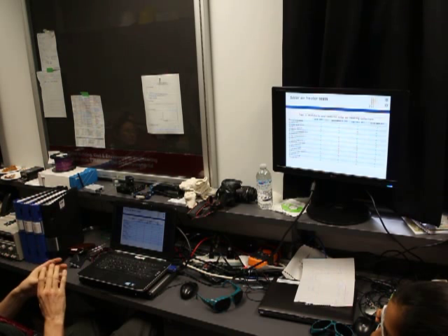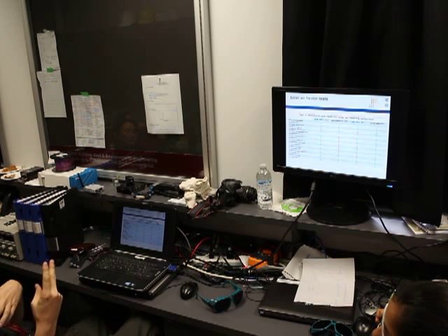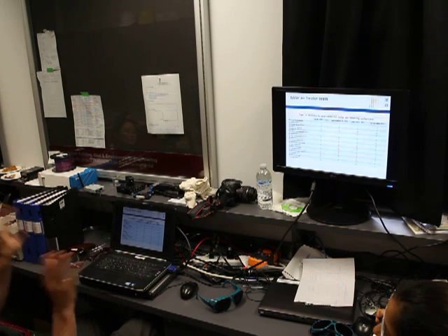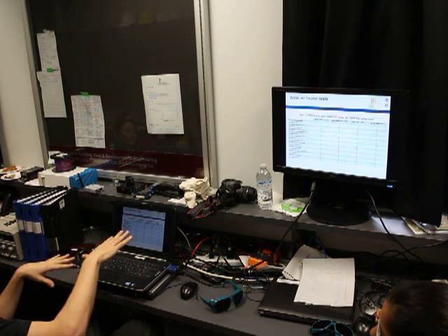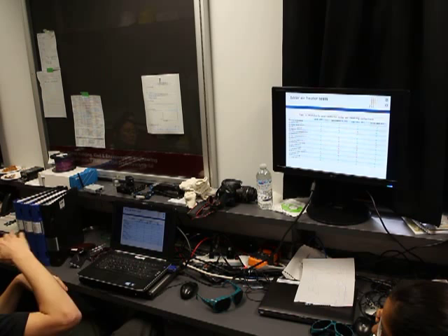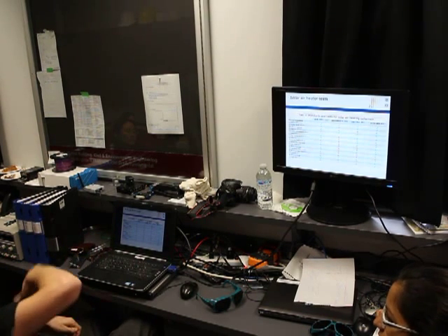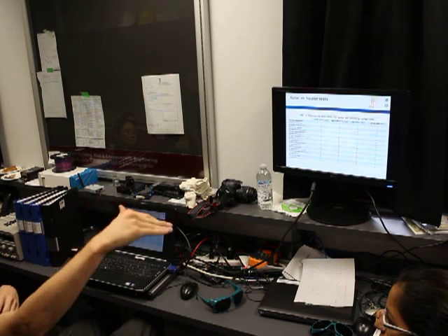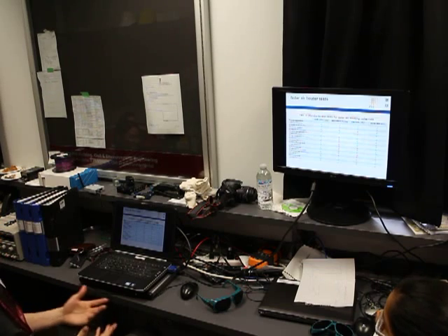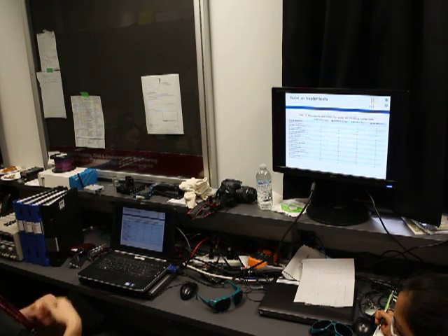Actually, it's a bit funny. There are three different ways to determine the thermal capacity. One is, for example, putting the collector in the sun, having a cover so it is not illuminated, having it at a certain temperature level, taking the cover away, and then waiting for the time till it stabilizes. I like that way, but nobody does it that way, because it's an additional test.